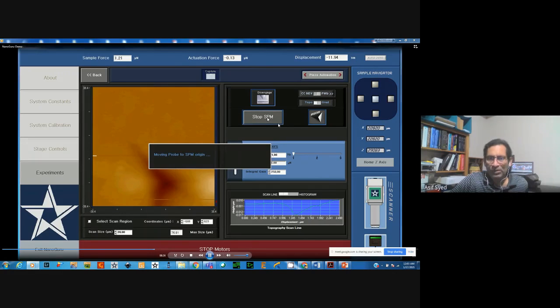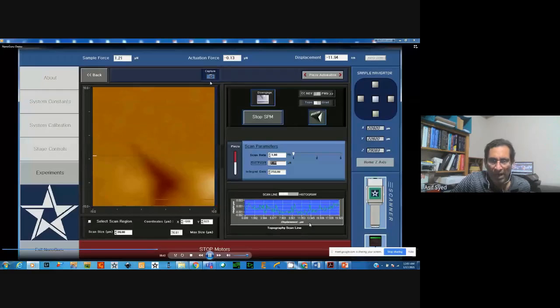Now when you engage and start the image, this window will pop up, and it will start to image from the bottom to the top. You can see it line by line, and you can see the line profile here. As it images, you can see the profile line by line, and it is constructed to give you the 2D image of the surface. So now it is scanning from the bottom to the top. This is a 10 by 10 micron size image. No, sorry, 20 by 20 micron size image.